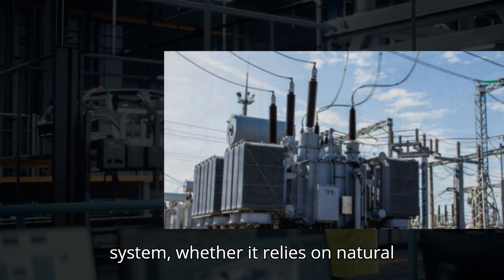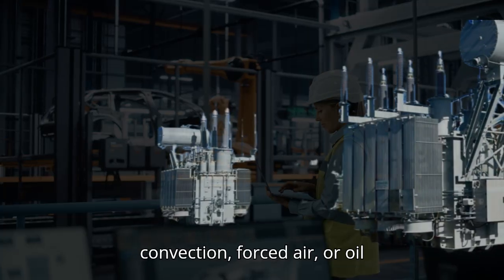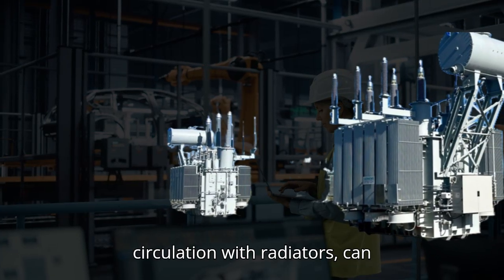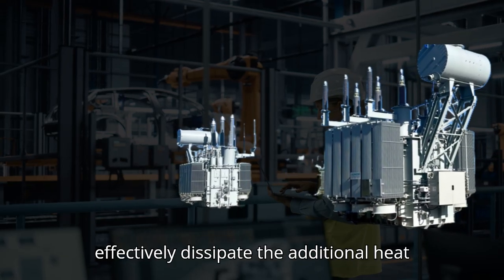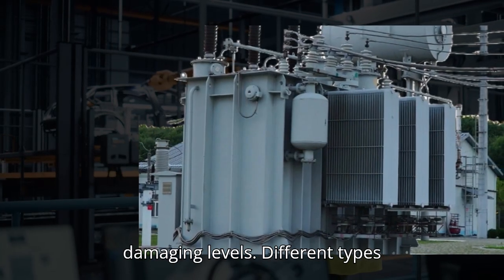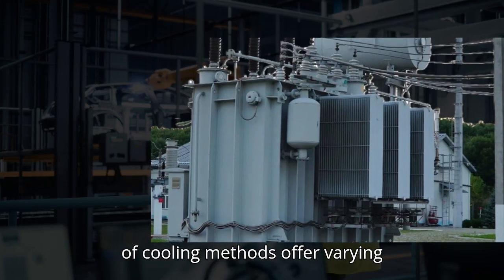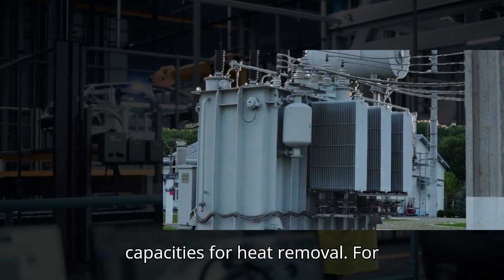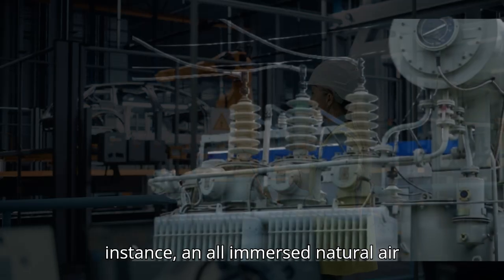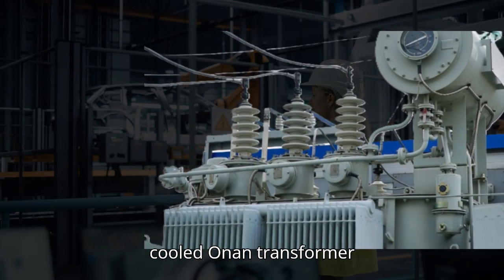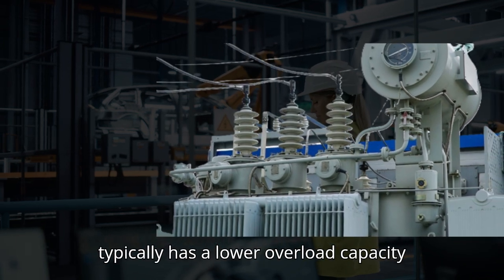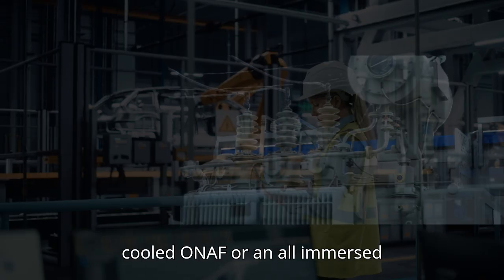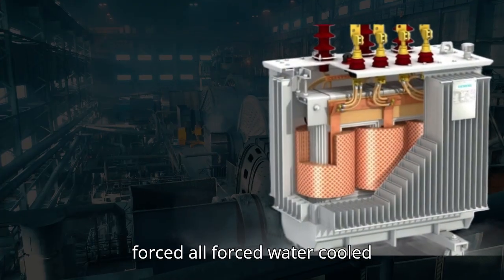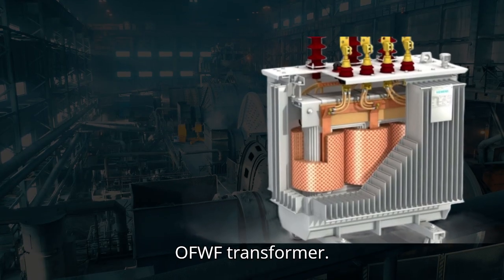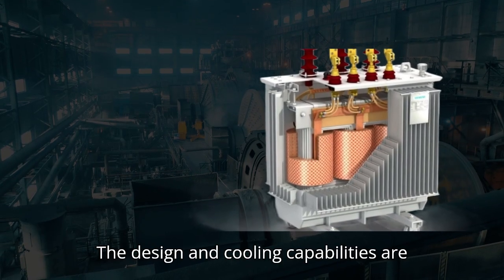Similarly, an efficient cooling system, whether it relies on natural convection, forced air, or oil circulation with radiators, can effectively dissipate the additional heat generated during a short-term overload, preventing the temperature from reaching damaging levels. Different types of cooling methods offer varying capacities for heat removal. For instance, an oil-immersed natural air-cooled (ONAN) transformer typically has a lower overload capacity compared to an oil-immersed forced air-cooled (ONAF) or an oil-immersed forced water-cooled (OFWF) transformer.